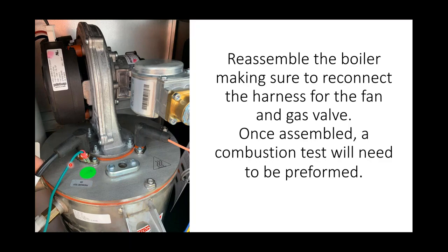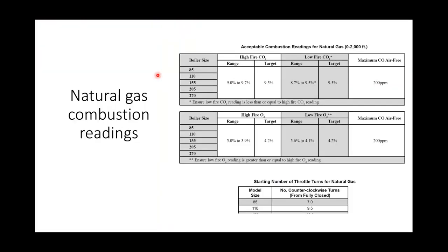Once everything's reassembled, again, we want to make sure that gas valve is in the I position. We put our hose back on. We have our 24-volt harness plugged back in. Get the unit back together, and we want to get it fired and run a combustion test. Again, it's in the beginning. We should have done one. We want to make sure that the combustion's on or close to what it originally was, or bring it back into spec.